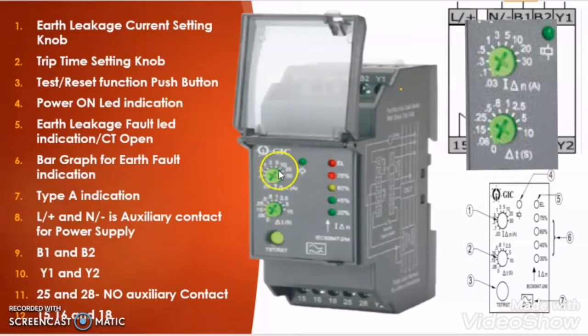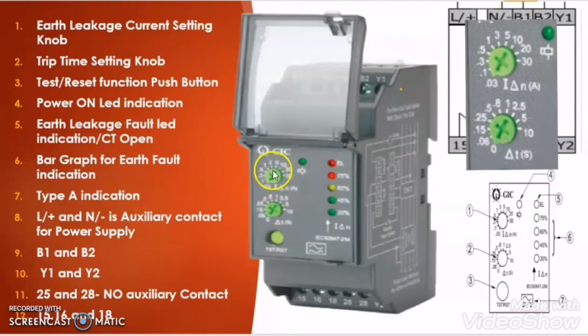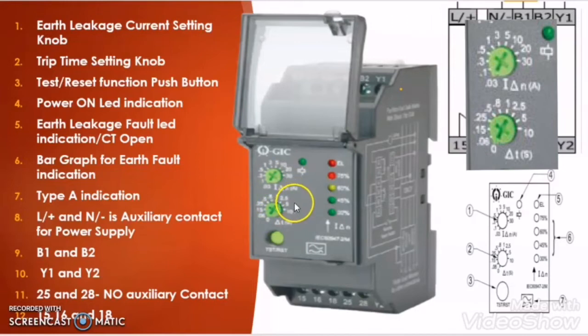If this 10 Ampere of earth leakage current persists for more than 5 seconds, then the earth leakage relay will give command to the circuit breaker or to the contactor to trip or to break its contact. So the time setting provides a hold time for the earth leakage current, and when that earth leakage current is prolonged beyond the set time, the earth leakage relay will give command to break the circuit.